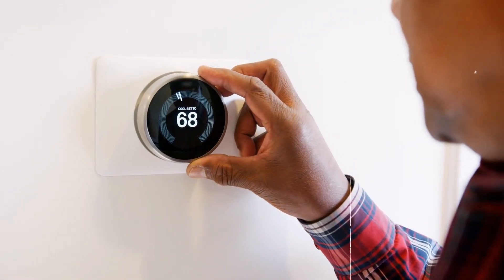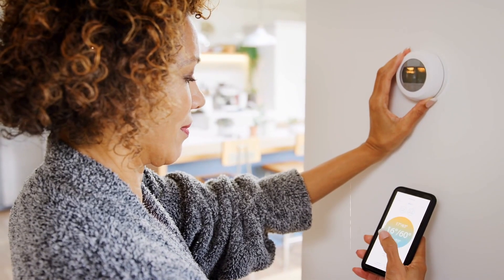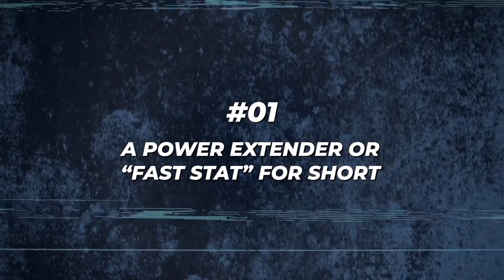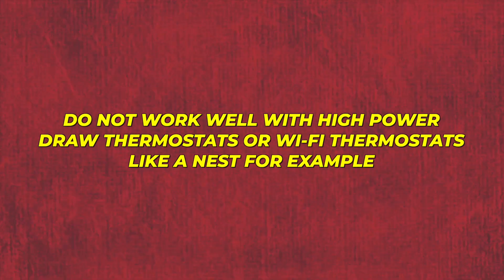Having a five-wire low voltage wire run to your thermostat gives you maximum compatibility with thermostats and thermostat settings. But if you're in a situation where you can't run a new wire, there are a few options. One is called a power extender or fast stat, which adds wires via a relay installed inside the furnace cabinet, allowing you to use an existing two-wire system and convert it into a five-wire thermostat. The downside is they are not very efficient and oftentimes glitchy, and they typically do not work well with high power draw or Wi-Fi thermostats like a Nest, but are an okay option for a basic battery-powered thermostat if you're in a pinch.